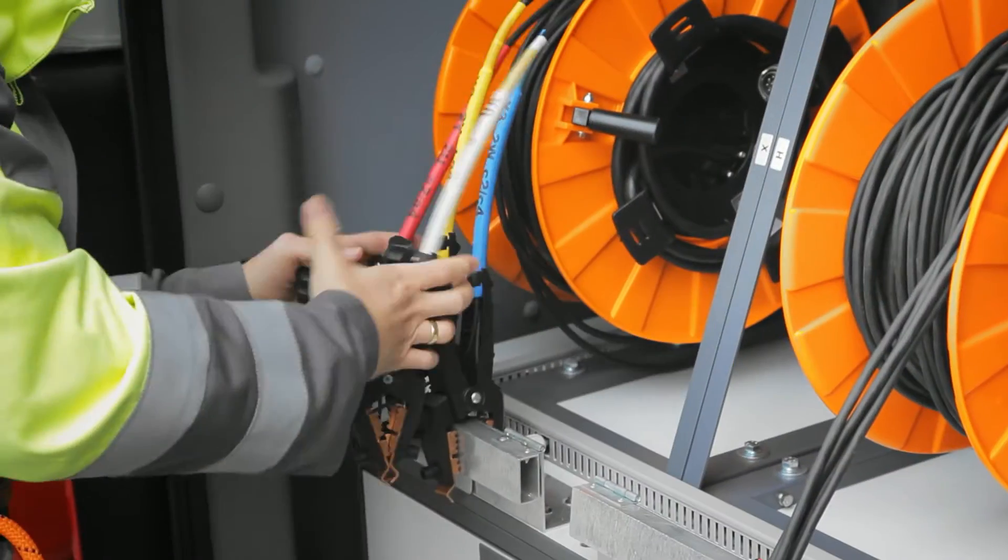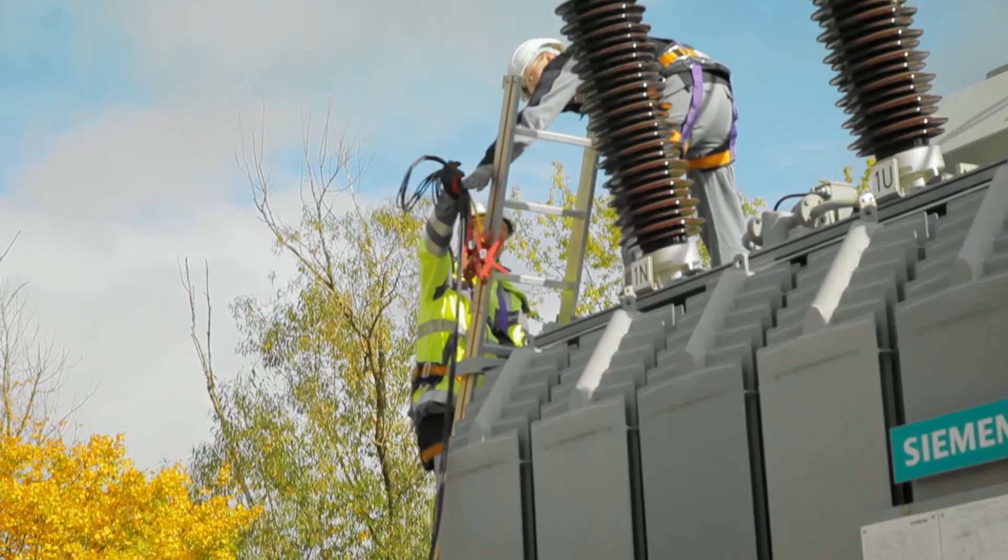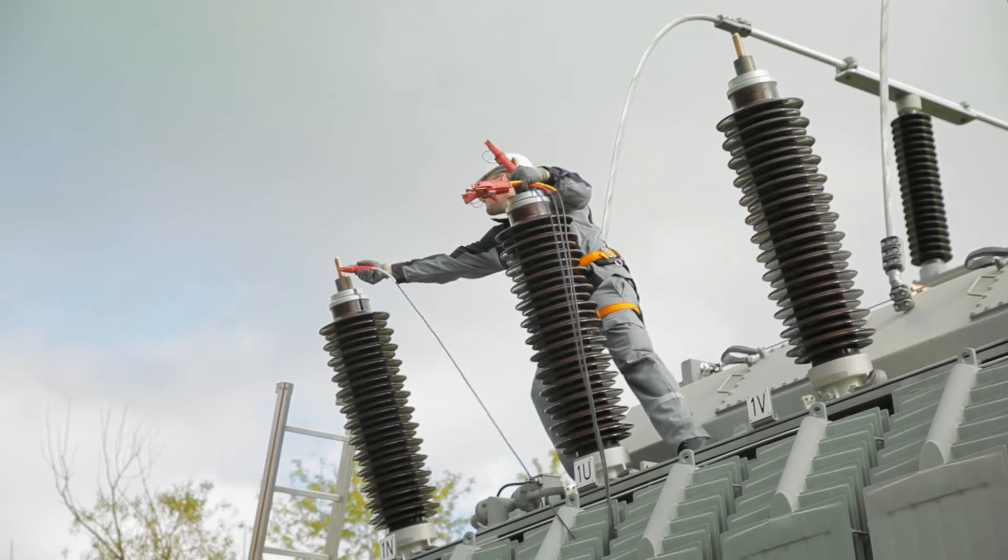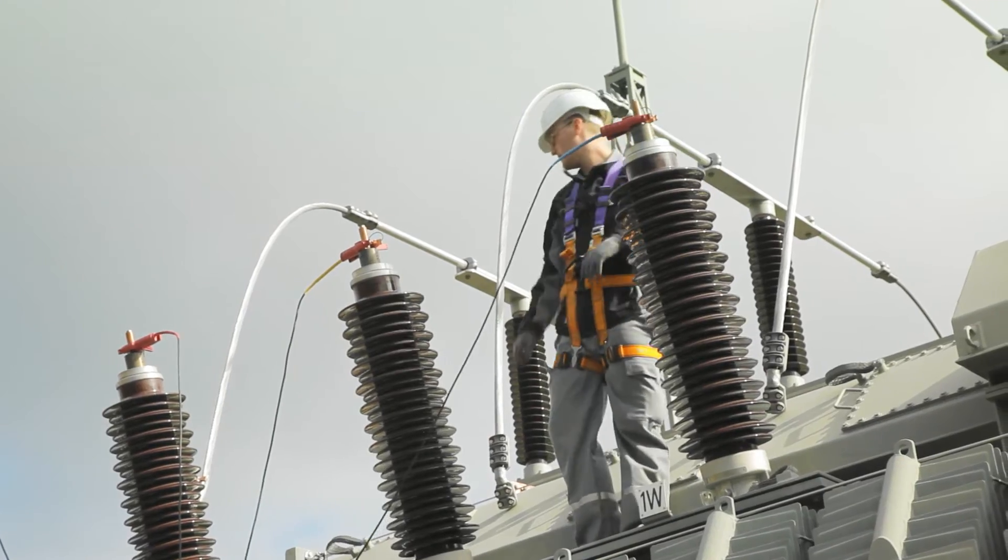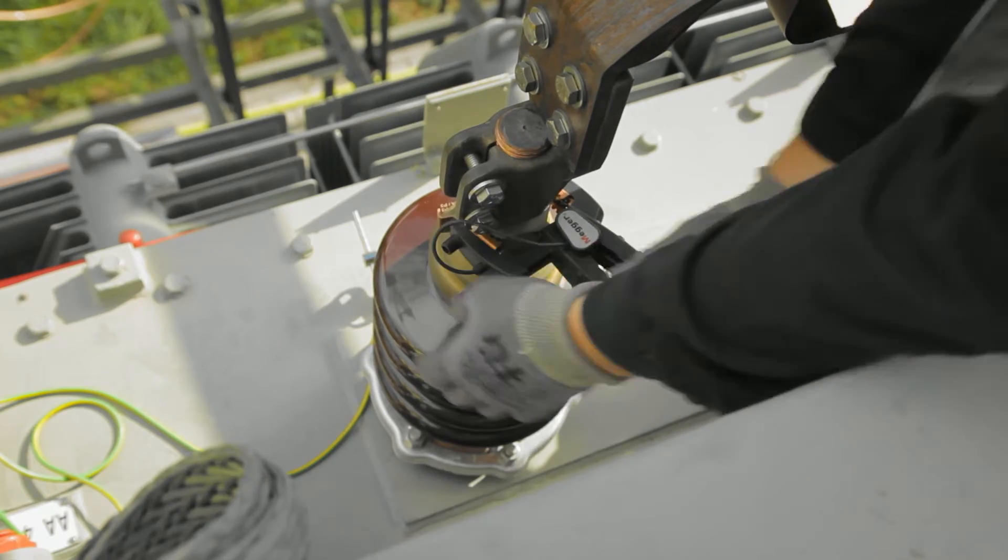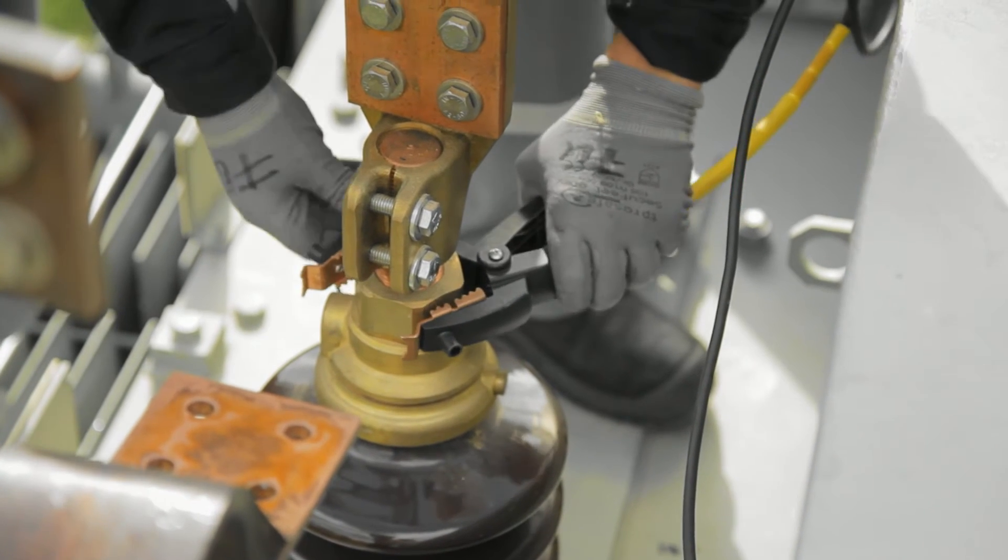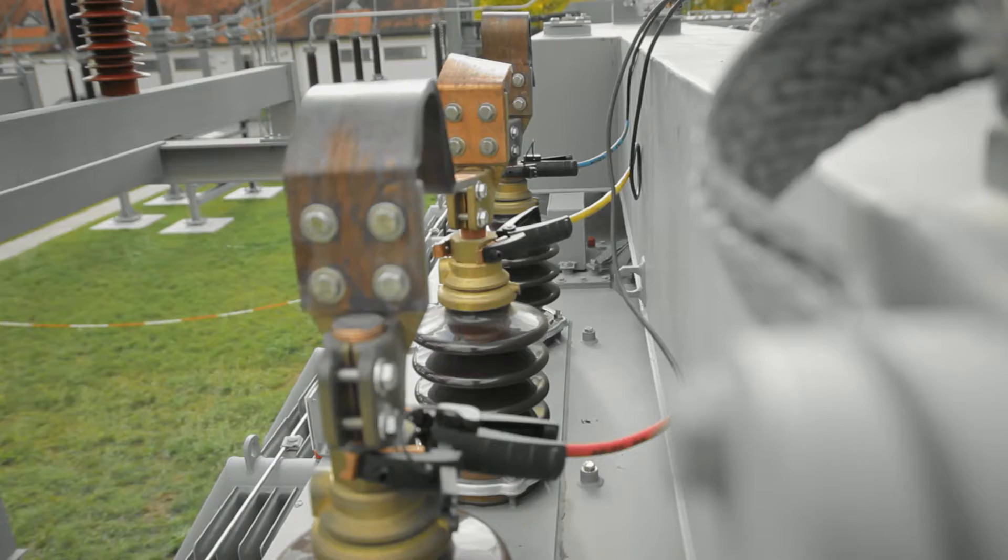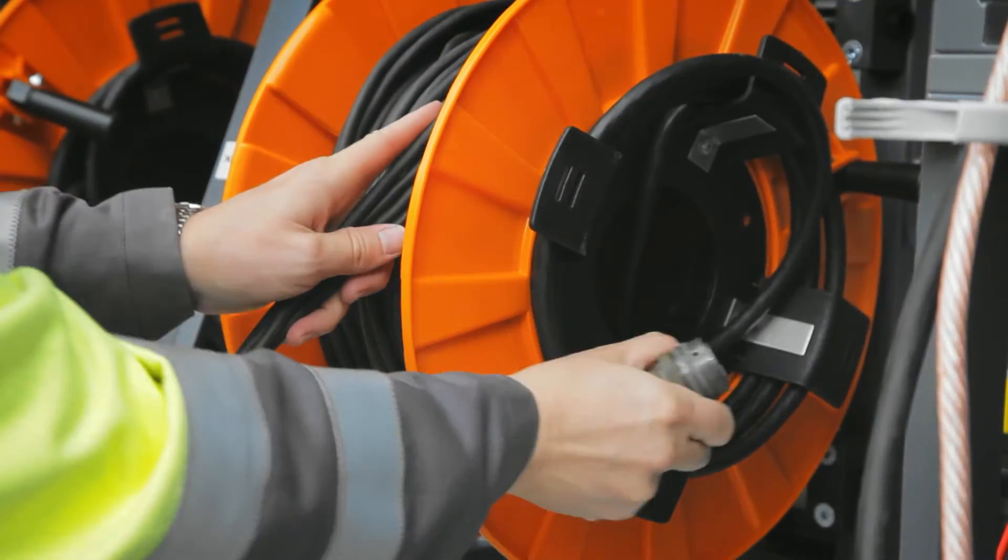Turns ratio and winding resistance are low voltage tests performed on every winding individually. Usually, they are done to assess the condition of windings, contact points and the proper operation of tap changers. Winding resistance and ratio measurements should be performed in all tap positions.